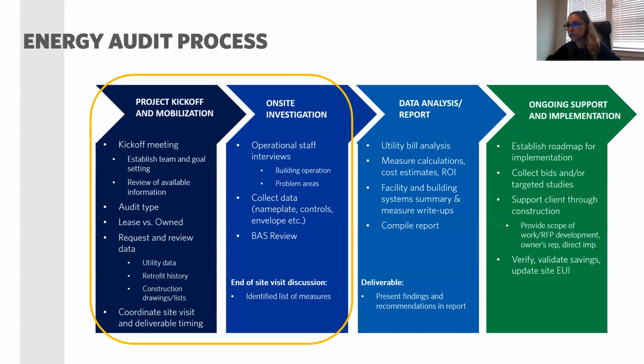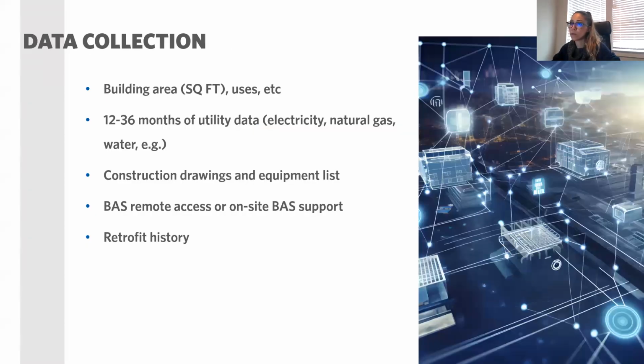The next step is getting into the site investigations and the site visits. Typically we ask for at least 12 months of utility data, and hopefully 36 months, along with construction drawings and any other nameplate information that is available. However, we rarely obtain all this information in advance. It could be based on the age of the building, or the property management may have changed a lot, so they do not have this information anymore. For the BAS, if we can get remote access, it's perfect, but sometimes we have to get screenshots or any information we can on site.